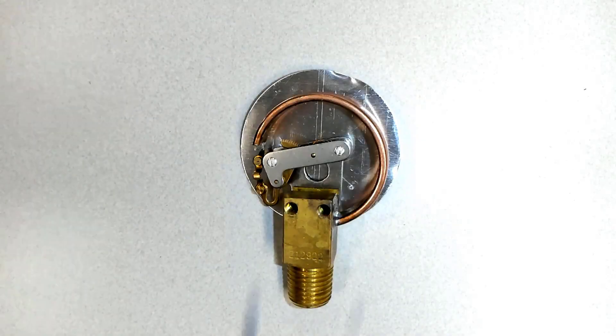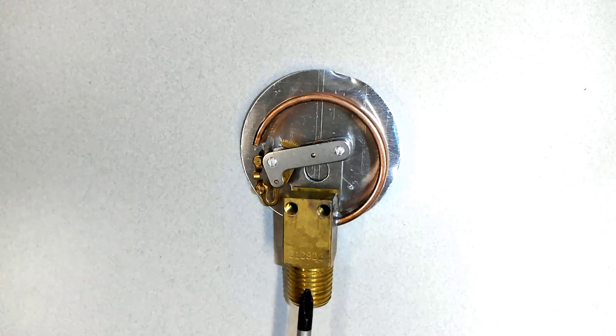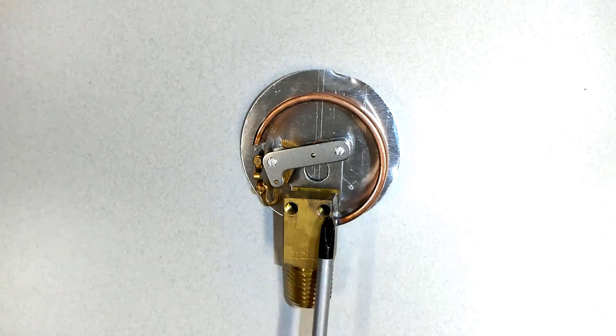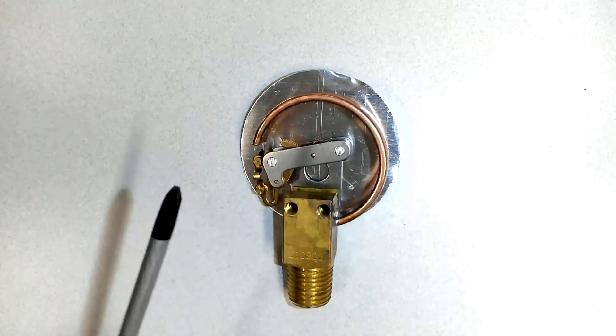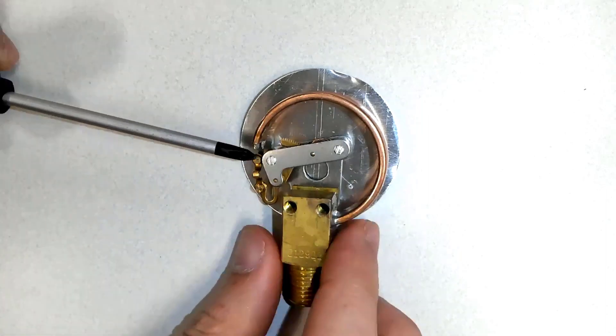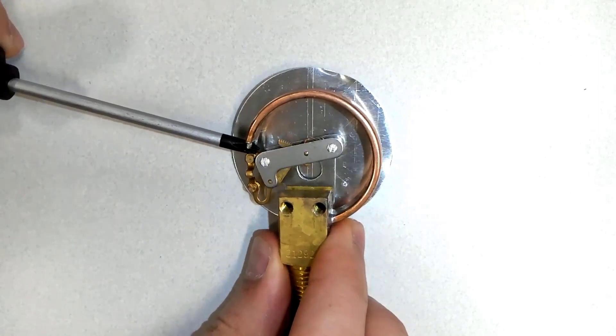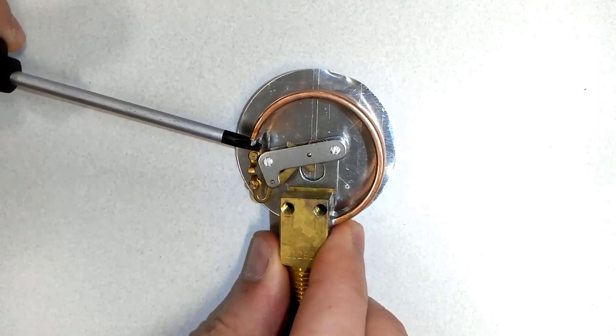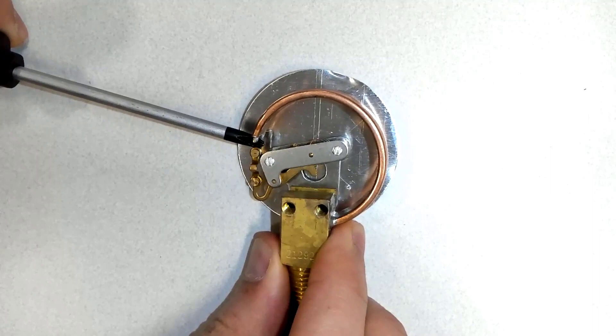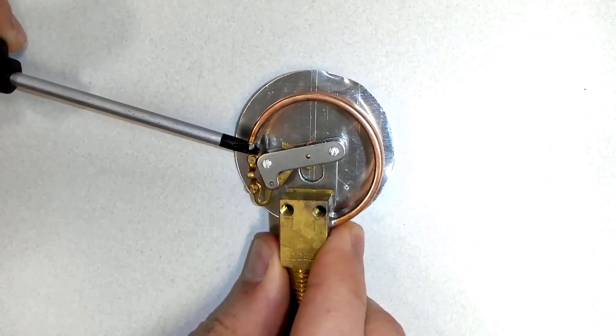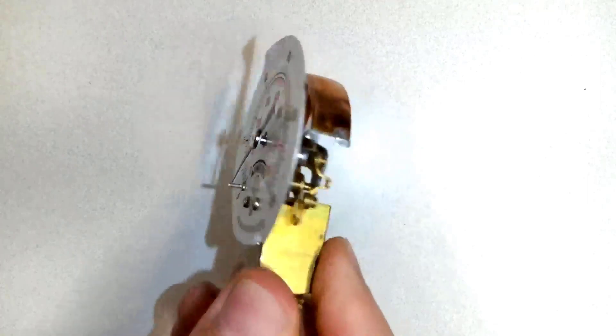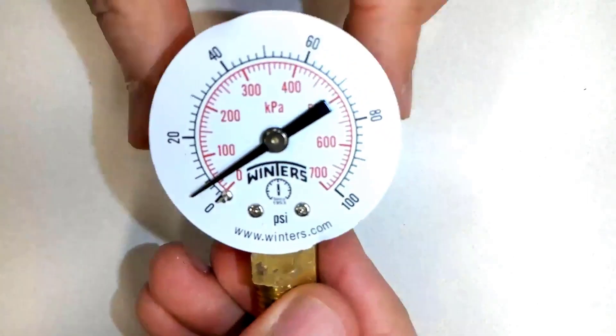Water or fluid goes inside the socket, then into your C-shaped Bourdon tube, and tries to straighten the tube. As it gets straightened, the gear comes into contact with the pinion, which is connected to the pointer.